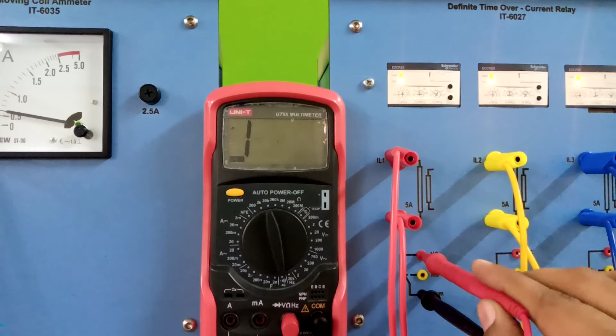So you can connect these two terminals to your PLC. Again, these two terminals can be connected, the normally closed and the common. So in this case, when there is a short circuit or the fault condition, what will happen is that this connection will open and your relay will stop. We will simulate it, but as you can see now this is normally closed, but right now it's open. So let's reset the relays. I will again decrease my load.